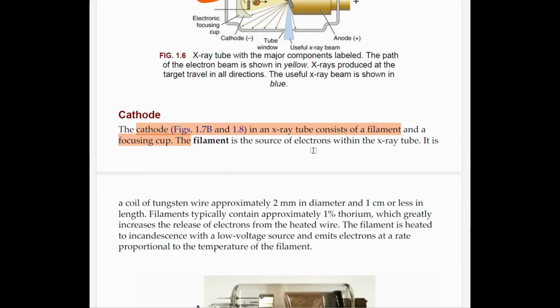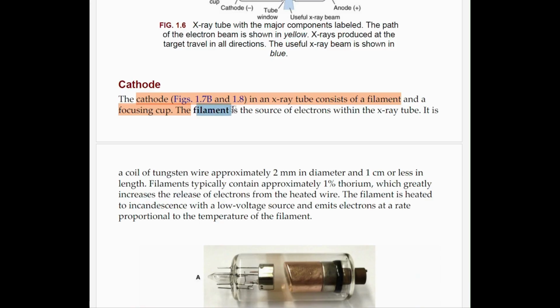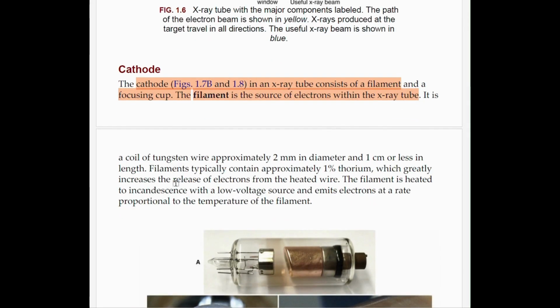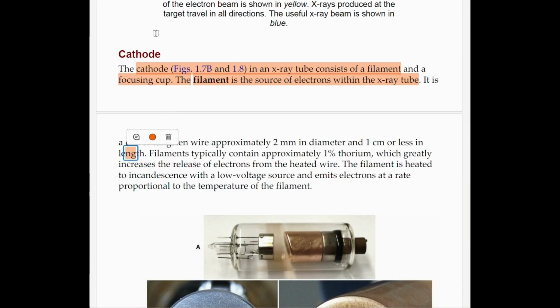The filament is the source of electrons within the X-ray tube. It is a coil of tungsten wire approximately 2 mm in diameter and 1 cm or less in length. So what are the important points in the cathode that we have understood so far? First, the cathode consists of the filament and the focusing cup. The filament is the source of electrons. It consists of a coil of tungsten wire 2 mm in diameter and 1 cm or less in length. The filament typically contains approximately 1% thorium, which greatly increases the release of electrons from the heated wire.